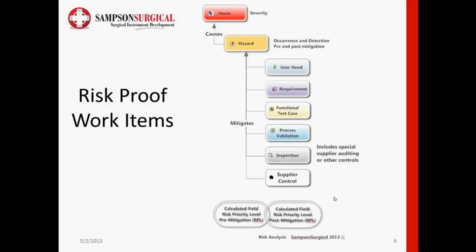And as we go through the development process, you'd start to do process failure mode analysis, design failure mode analysis, and different types of analysis methods to identify hazards that are specific to that harm in our device. So you'd start linking in, okay, this hazard is associated with that particular harm, and build the process out as you go along.